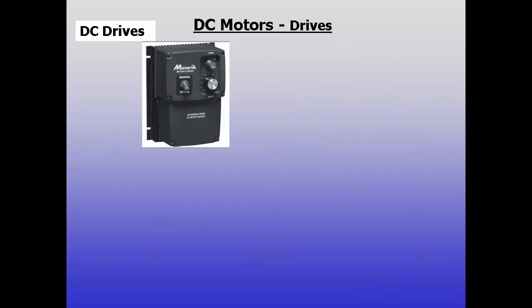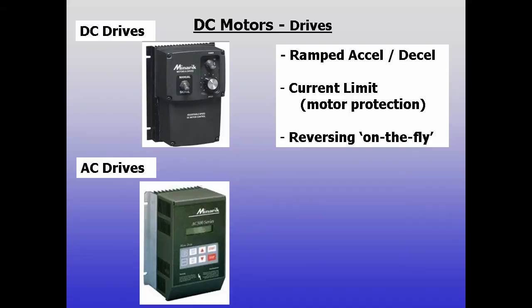As it turns out, DC drives were invented years before AC drive technology was introduced. As a result, many of the same features are on both. DC drives can ramp acceleration and deceleration and control outgoing current to protect the motor. And regenerative drives can provide contactorless reversing while a motor is turning.